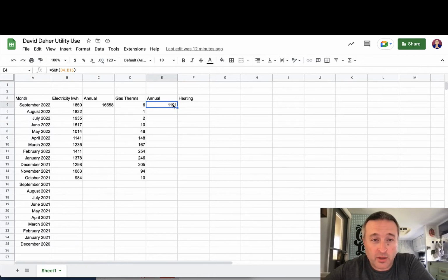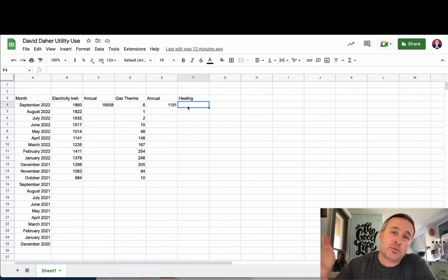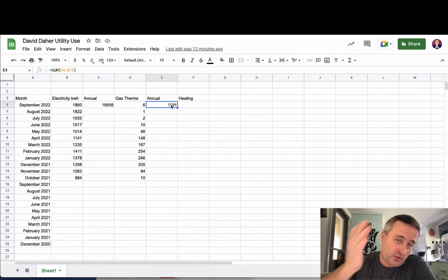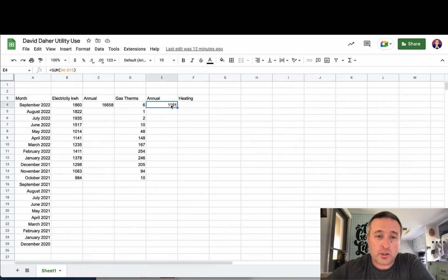This right here, because we know that the only thing that is gas is the furnace, we know that this 1191 therms is all heating. If you had water heat, say there was 10 therms a month of water heat, you'd subtract 120 from this, 10 times 12. So generally your water heat's going to be between 10 and 20 therms per month, unless you have a really big family or something's really screwed up.